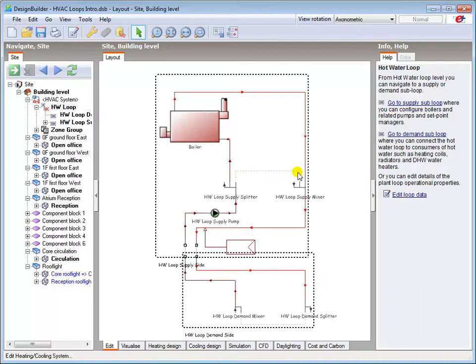represents a flow bypass. This is a protective measure found in real systems which allows water to bypass directly to the return side when there is no demand or flow in the system. There are additional splitter and mixer considerations for more complex systems, which again is covered in another tutorial.